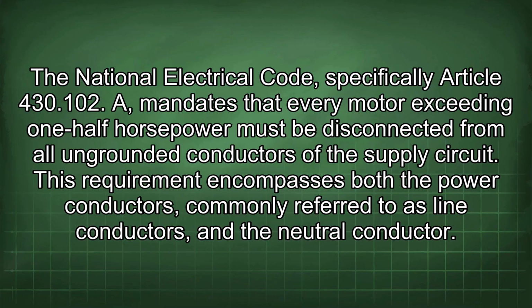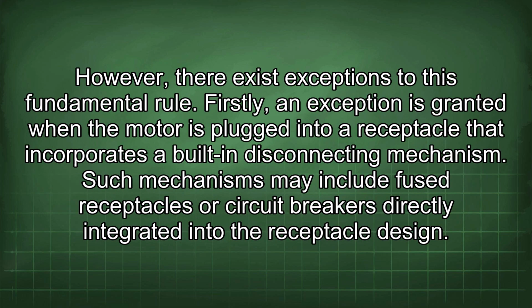The National Electrical Code, specifically Article 430.102(A), mandates that every motor exceeding 1/2 horsepower must be disconnected from all ungrounded conductors of the supply circuit. This requirement encompasses both the power conductors, commonly referred to as line conductors, and the neutral conductor. However, there exist exceptions to this fundamental rule.